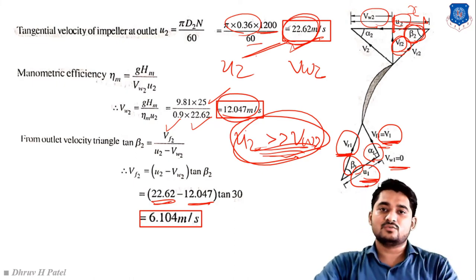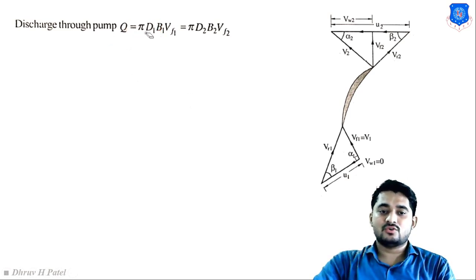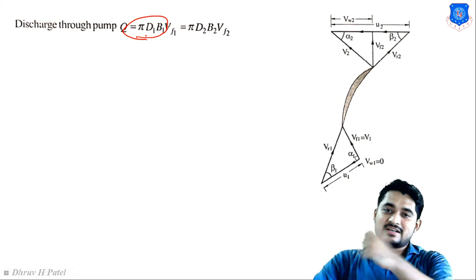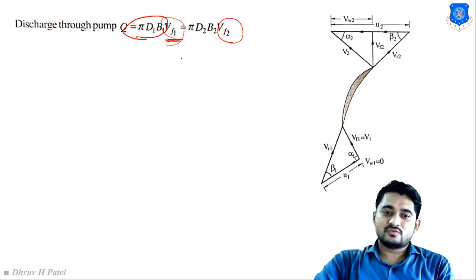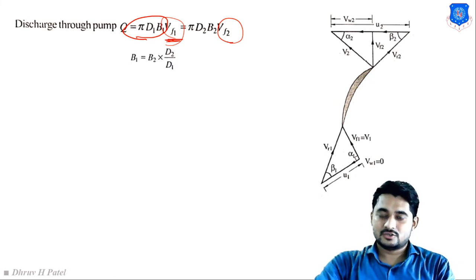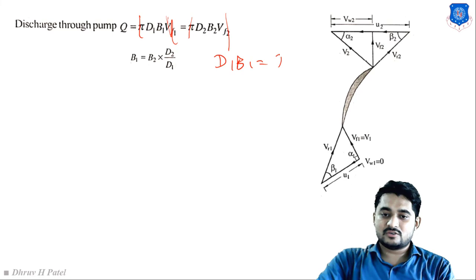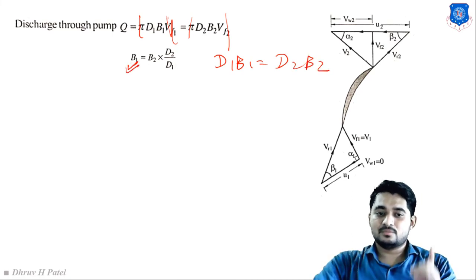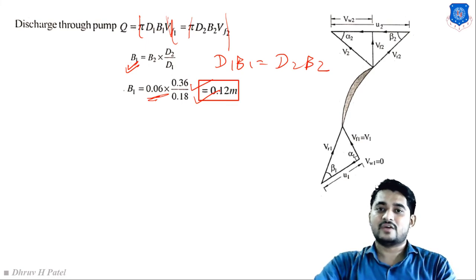From continuity: π d1 B1 V_f1 = π d2 B2 V_f2. Since V_f1 = V_f2, they cancel: d1 B1 = d2 B2. So B1 = B2 × d2 / d1 = 0.06 × 0.36 / 0.18 = 0.12 m. Width at inlet B1 = 0.12 m.